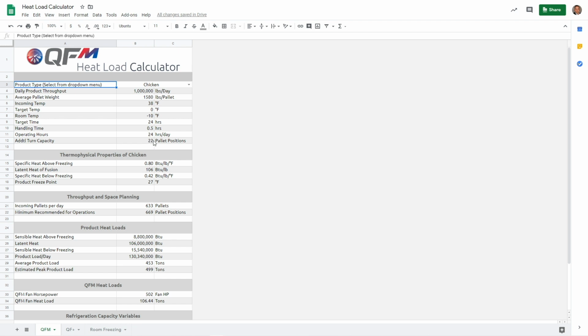Then the next cell is additional turn capacity. I'm just going to put one extra truckload of product in. And that helps the operation have some flexibility if they have loads that are coming in early. We like to have a home for every pallet as soon as possible when it hits the door. And obviously, you can adjust that number to whatever is suitable for the operation. The next group are the thermophysical properties of the material we chose, the chicken. So we start with specific heat above freezing.